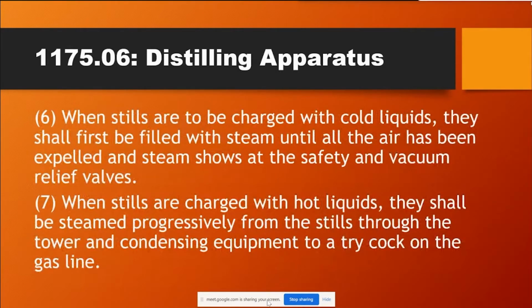When stills are to be charged with cold liquids, they shall first be filled with steam until all the air has been expelled and steam shows at the safety and vacuum relief valves. When stills are charged with hot liquids, they shall be steamed progressively from the stills through the tower and condensing equipment to a try cock on the gas line.